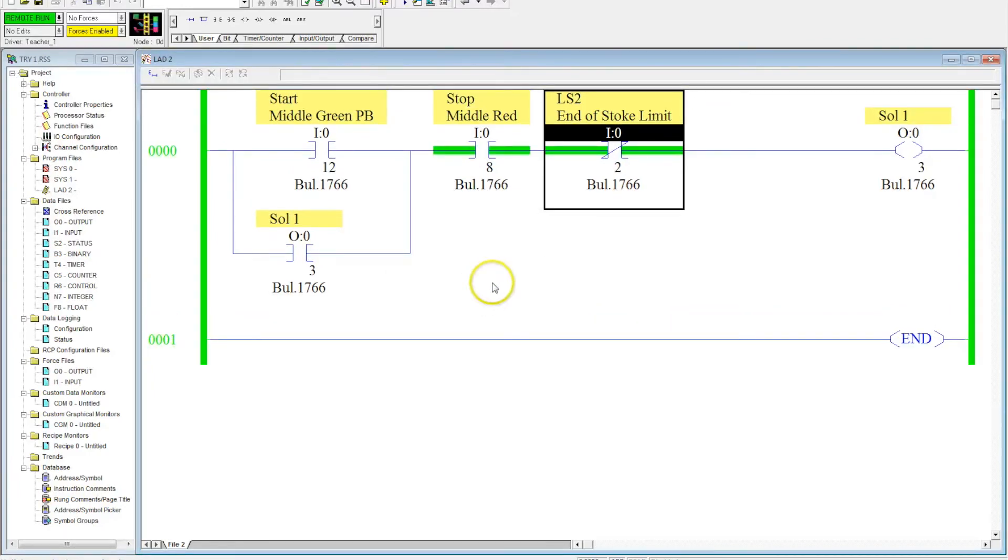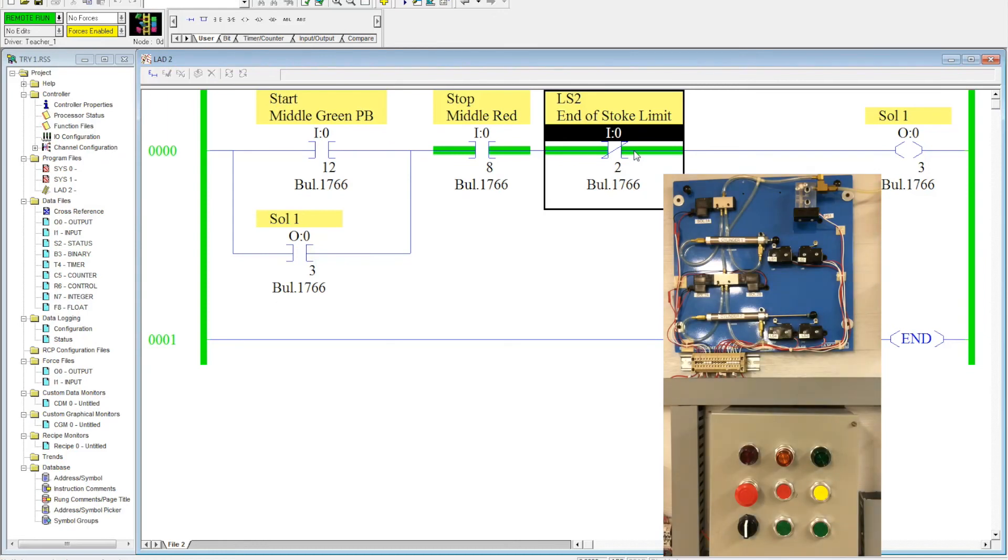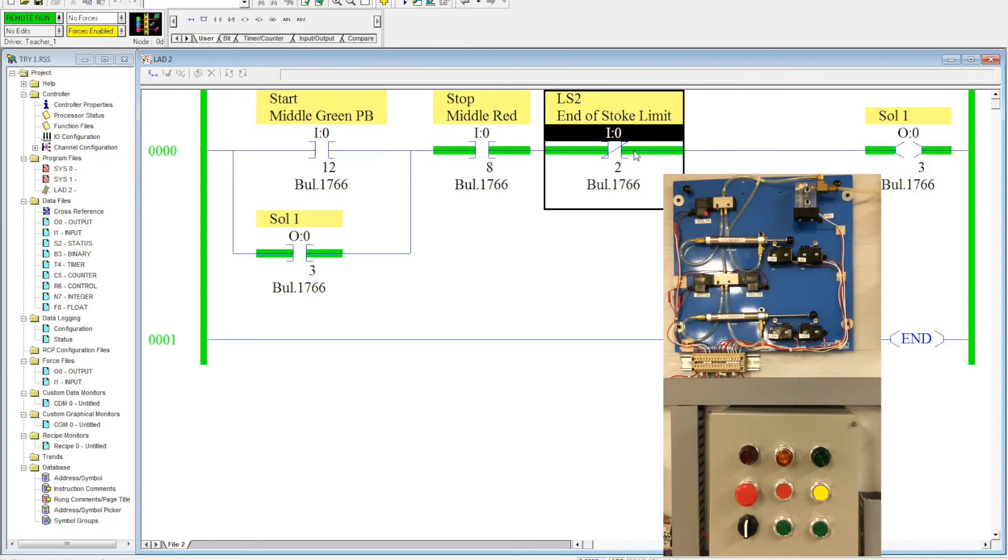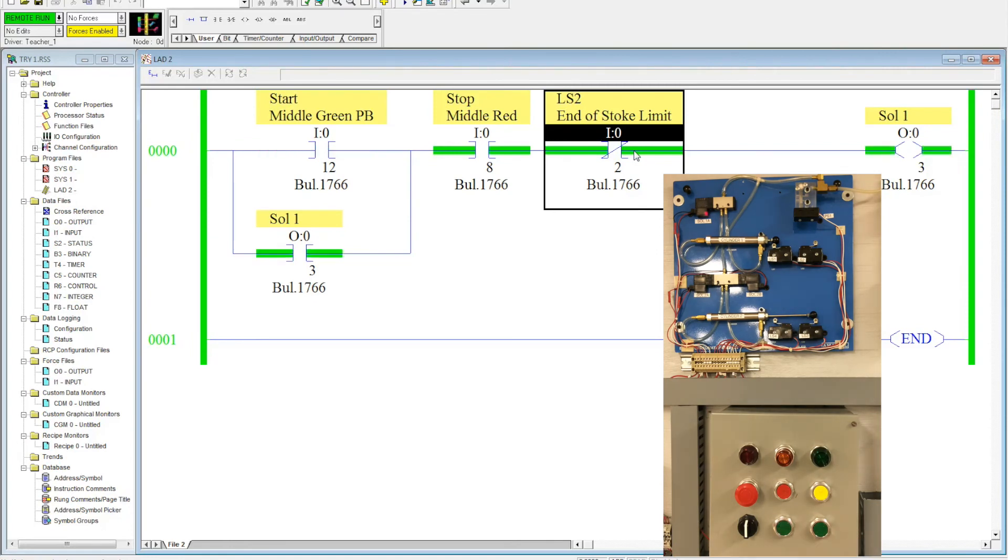So, now, I want you to notice a couple of things. Both of these are green, meaning that they're logically true. So, the path of logical continuity can run through these two. So, now, I'm going to come over, I'm going to activate the middle green button, and when I do that, when I activate the middle green button, it extends out, and when it hits LS2 at the very end of the stroke, it retracts. That momentary push is enough to drop the memory out and allow the spring of the directional control valve to shift the spool, retracting the cylinder. Let's watch it one more time.